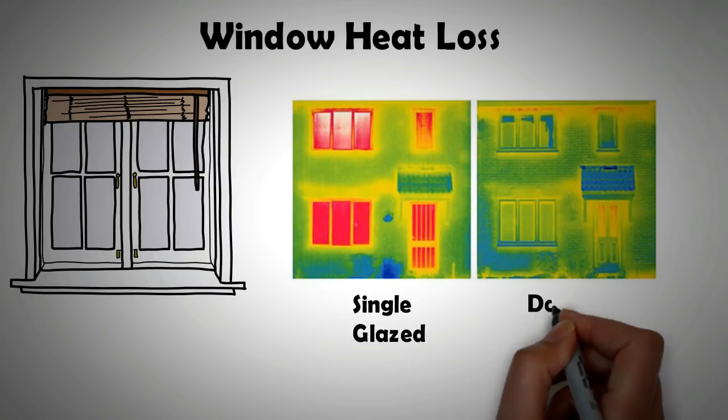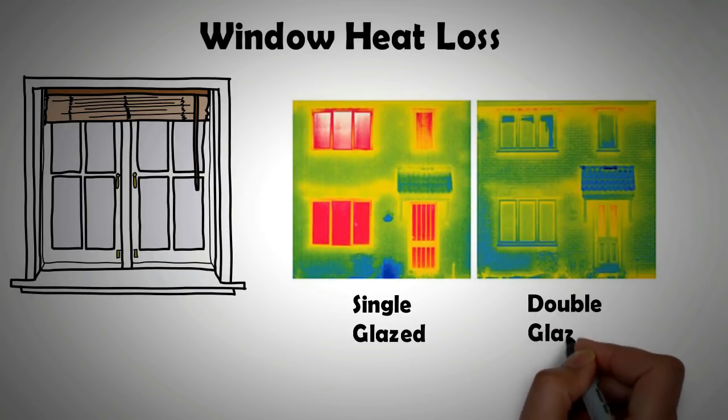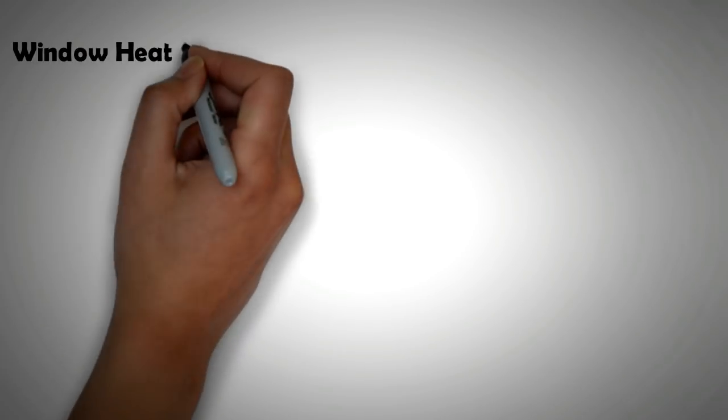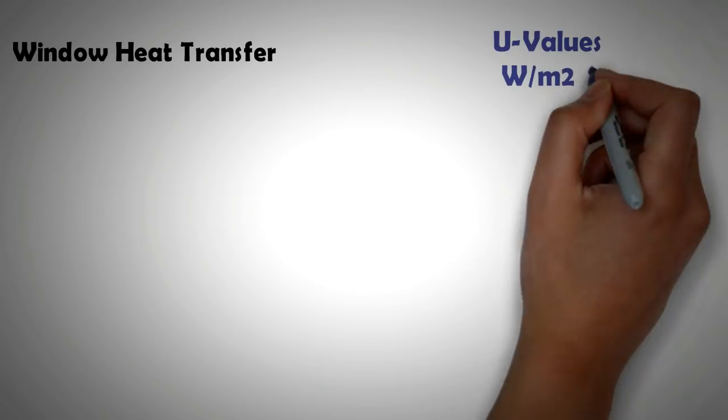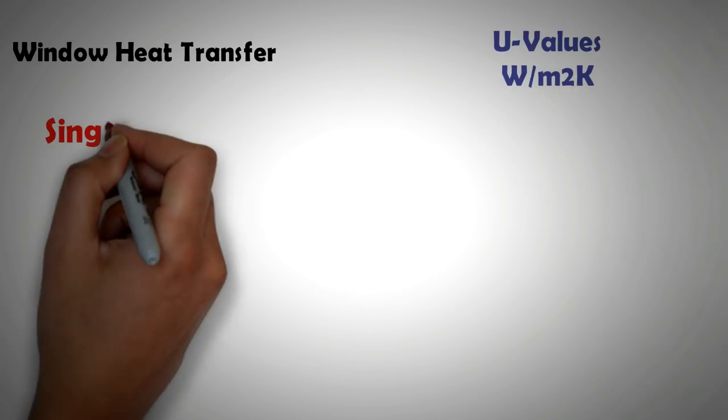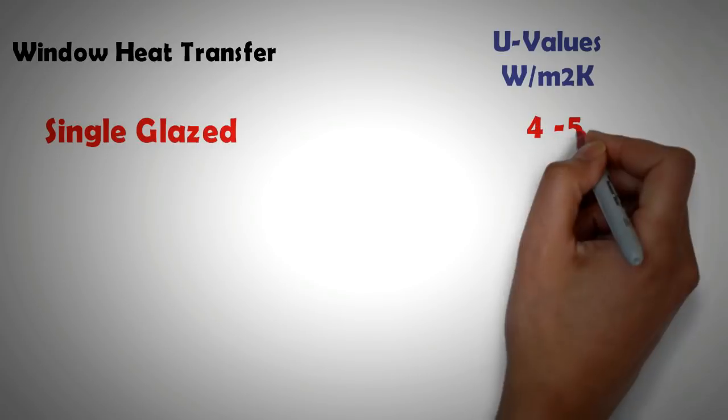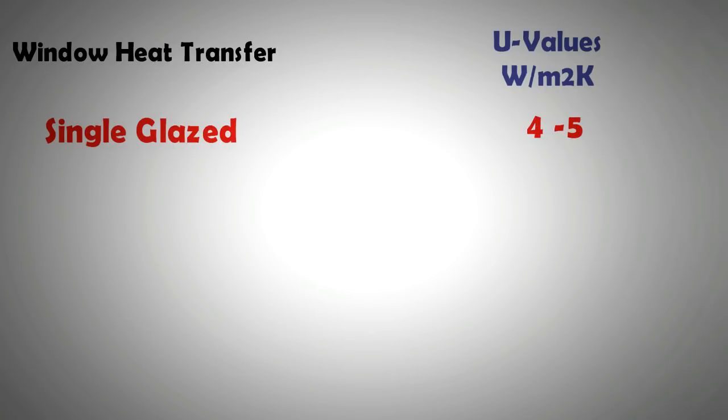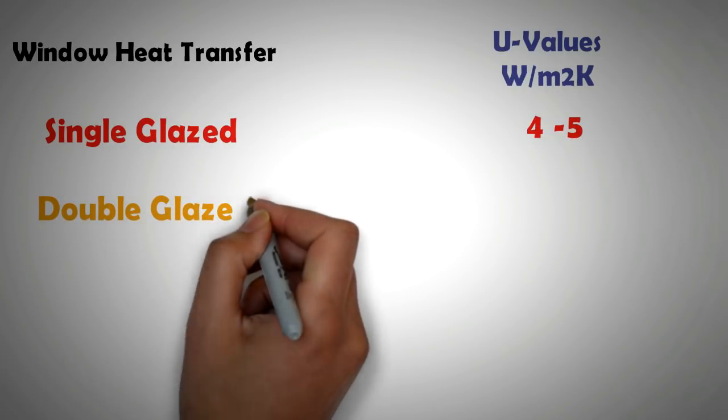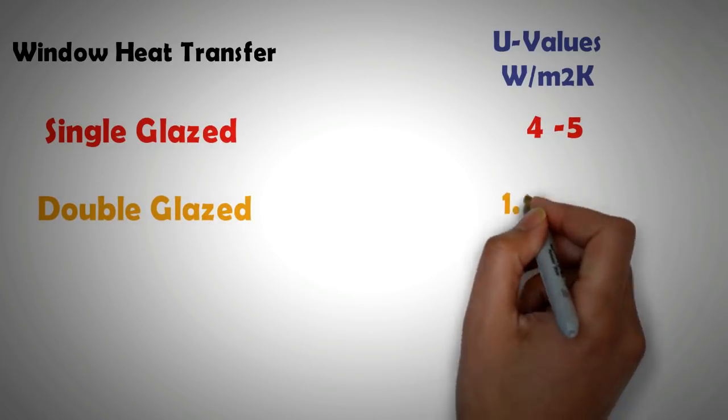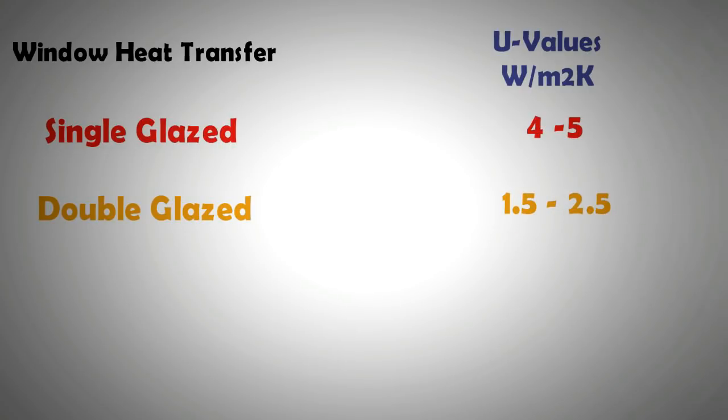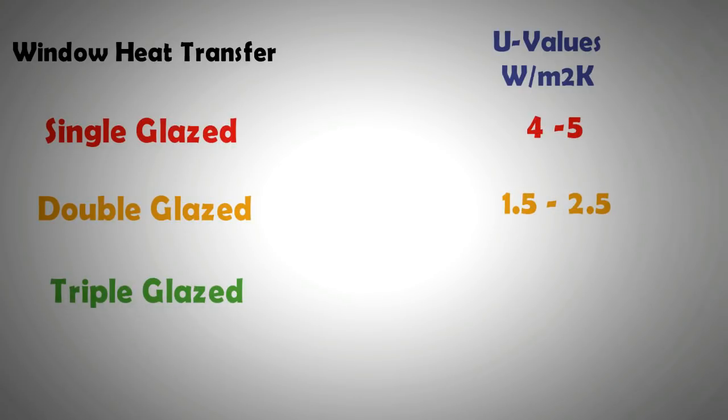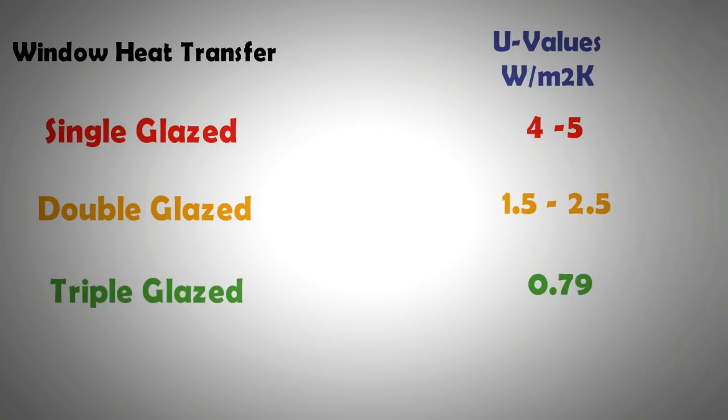The heat loss properties of a window are characterized by U value. A low U value is favorable. Just for comparison, the U value of single glazed window is around 4 to 5 watt per meter square per kelvin. The U value of a double glazed window is 2.5 to 1.5 watt per meter square per kelvin, while the U value of a triple glazed window can be as low as 0.79 watt per meter square per kelvin, meaning a triple glazed window can prevent five times less heat loss compared to a single glazed window.